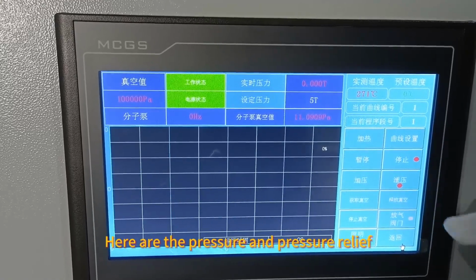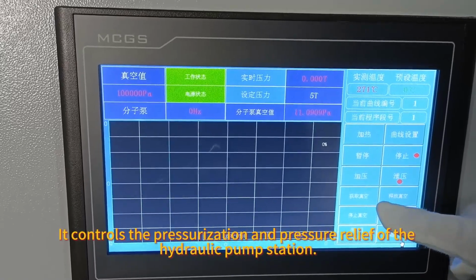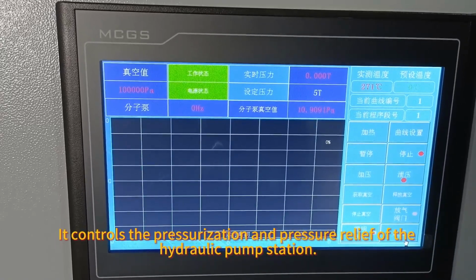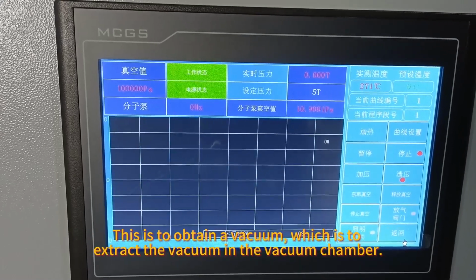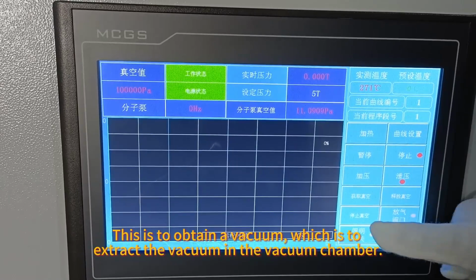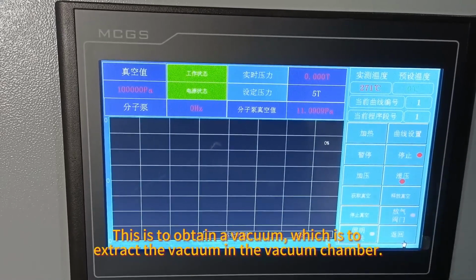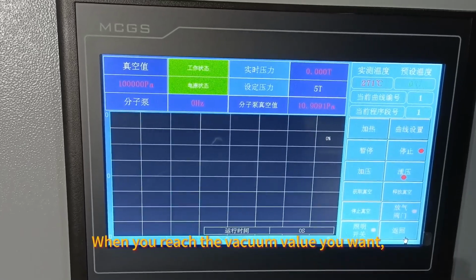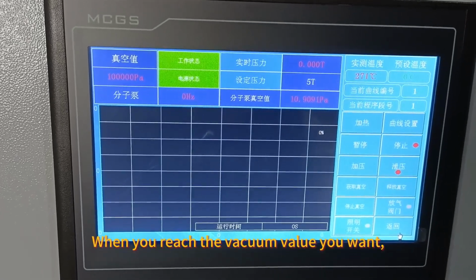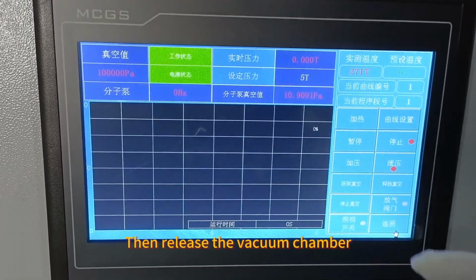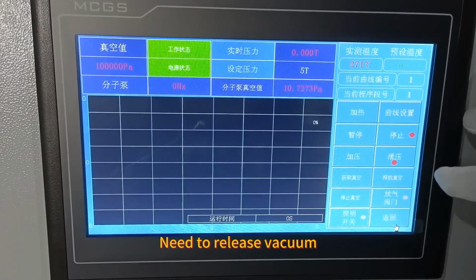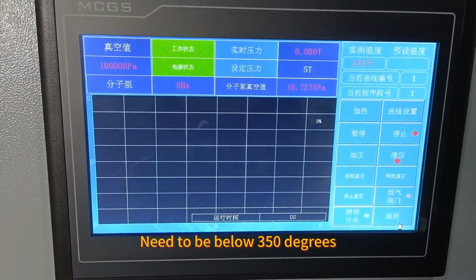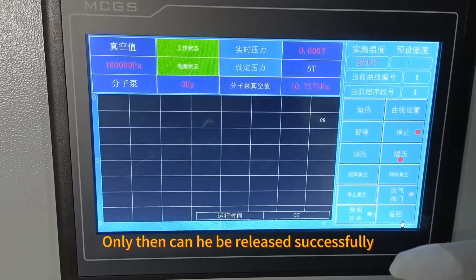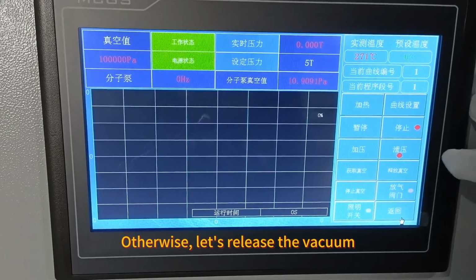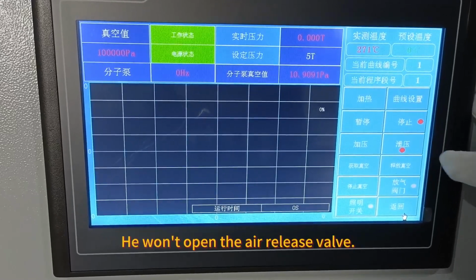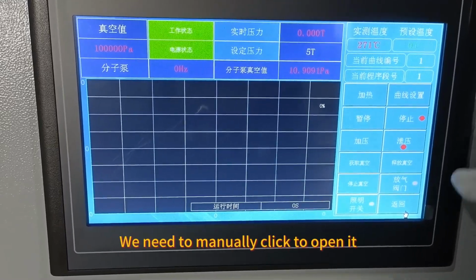Here are the pressure and pressure relief. It controls the pressurization and pressure relief of the hydraulic pump station. This is to obtain a vacuum, which is to extract the vacuum in the vacuum chamber. When pumping, or when you reach the vacuum value you want, stop vacuuming. Then release the vacuum chamber. To release the vacuum, the temperature needs to be below 350 degrees. Only then can it be released successfully. Otherwise, when we release the vacuum, it won't open the air release valve. We need to manually click to open it.